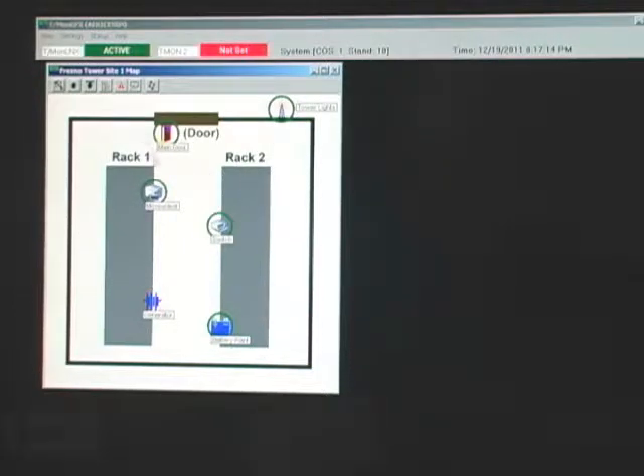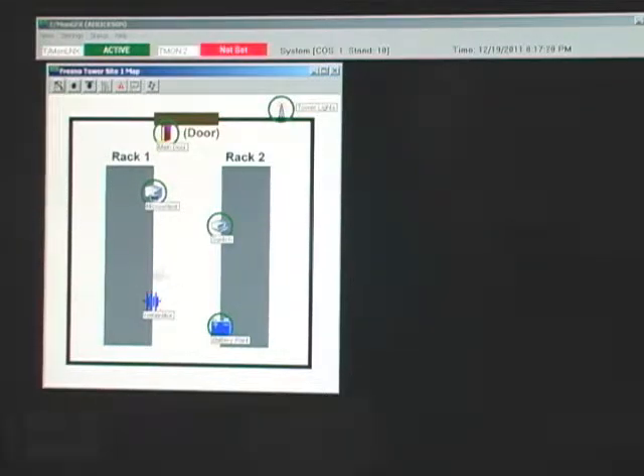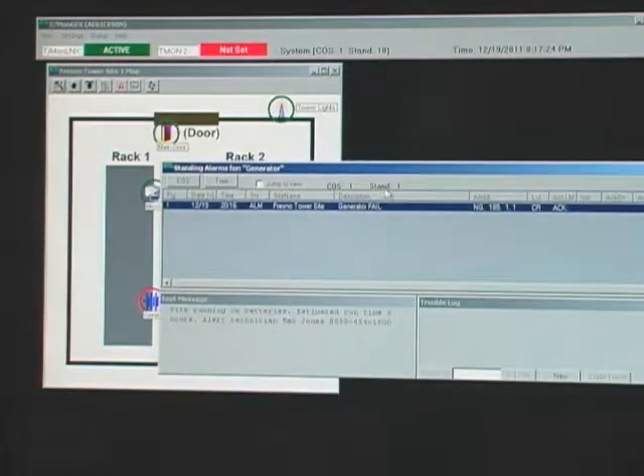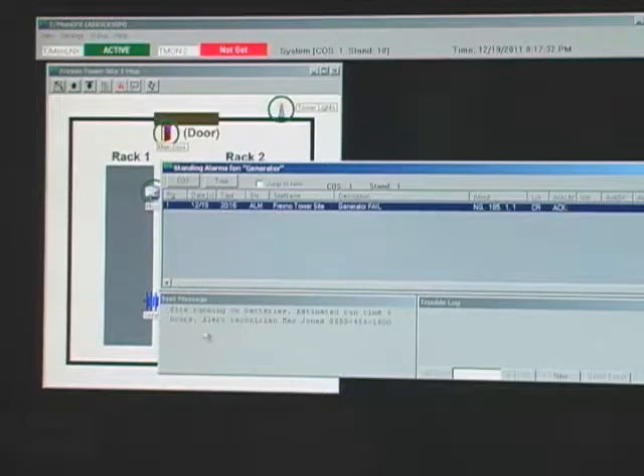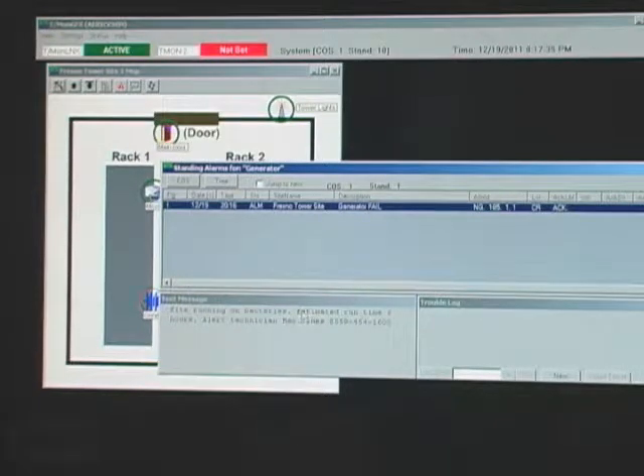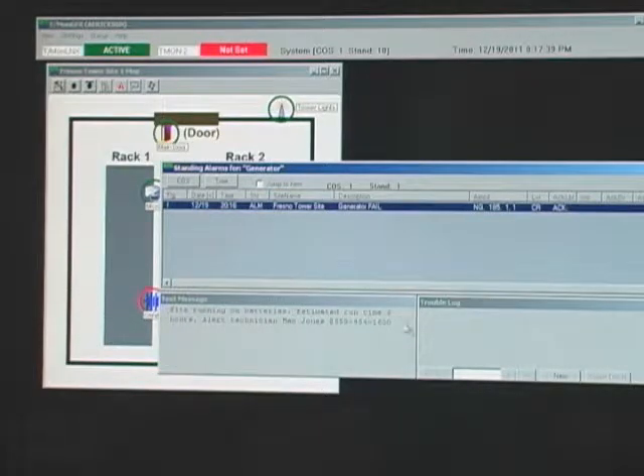I have a variety of icons here that are not in a failed condition — tower lights, the main door sensor, microwave switch. In this case, it's the generator that has the problem. So I'll click on Generator, and you'll see in this detail window that I have a generator fail at the Fresno Tower site. I get all the information I need, and I've actually associated a text message with this icon telling me that the site is probably now running on batteries with an estimated runtime of six hours, and I should alert a technician at this phone number.